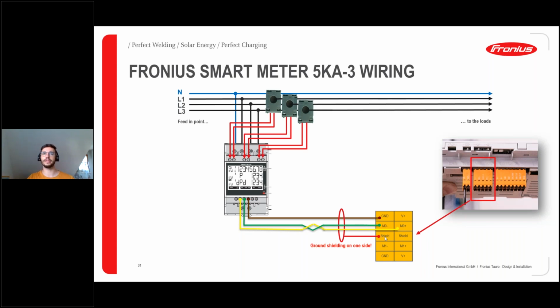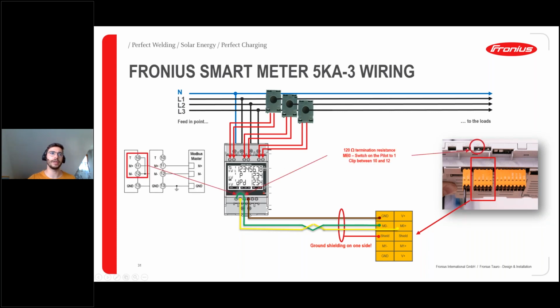And the third one is, please make sure to set the 120 ohm resistor at the end of our data communication. So on a Modbus line, we have a serial connection of components, and at the end, we always need to make sure to set the 120 ohm resistor. So in our case, it's the smart meter and the Tauro device. And here we have a very easy way to do this on the smart meter, because the 120 ohm termination resistance is already set within the Tauro. It's already built in. And the only thing we need to do is to set a small cable bridge here, like we can see here, and then we have activated it. So that's a very fast and easy way to do it on the smart meter.